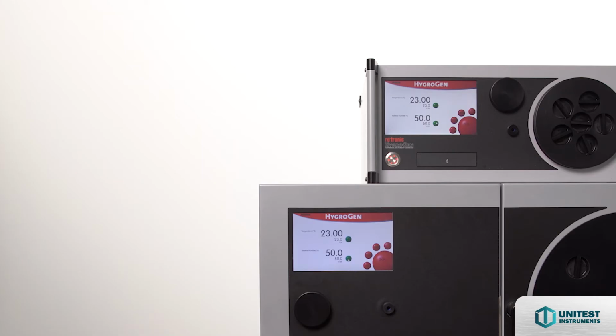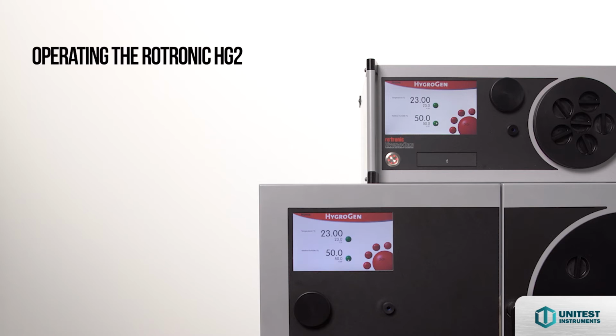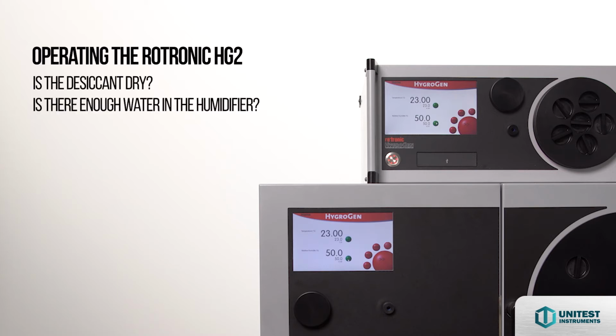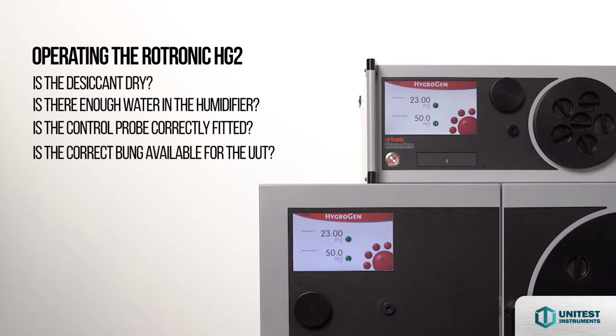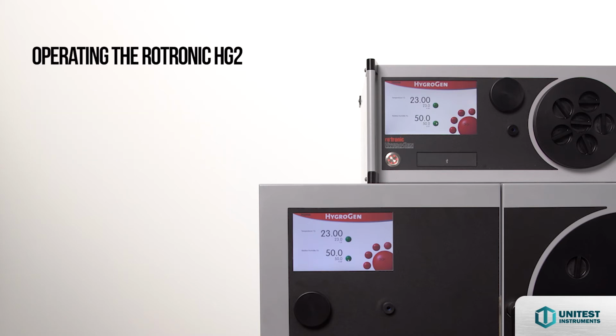Operating the HG2 is very simple and straightforward. All you have to consider are the following. Is the desiccant dry? Is there enough water in the humidifier? Is the control probe correctly fitted? Is the correct bung available for the UUT? The on-screen electronic water level indicator, desiccant condition monitoring level, and continuous feedback from the control probe makes it easy for the user to check all of these parameters before any test conditions are started.